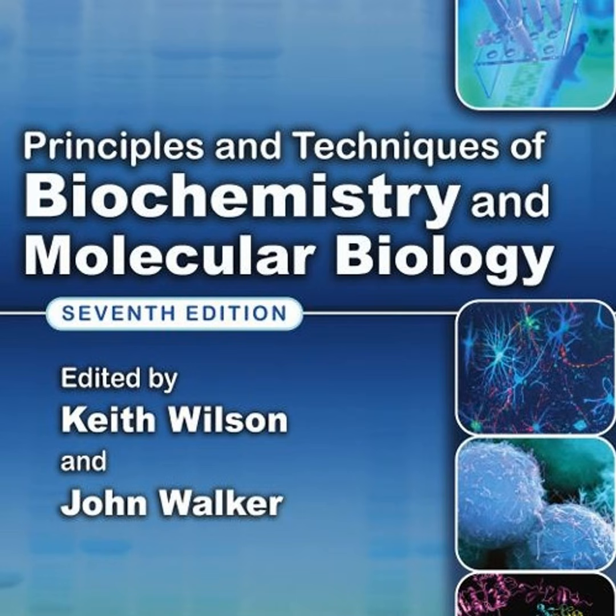Wait, watch it while it spins? Yeah. Analytical ultracentrifuges have built-in optical systems, so by monitoring how a macromolecule moves through the fluid while it's spinning, we can determine its relative molecular mass and its physical shape in its native, completely unaltered state. That is wild. And once we know its mass, we usually want to see it, right?